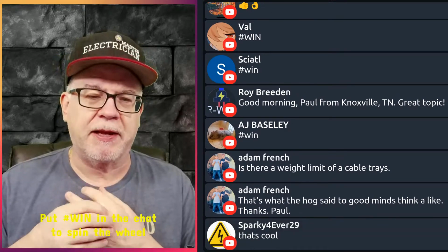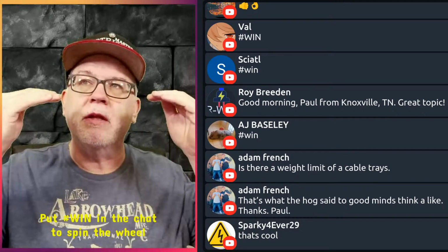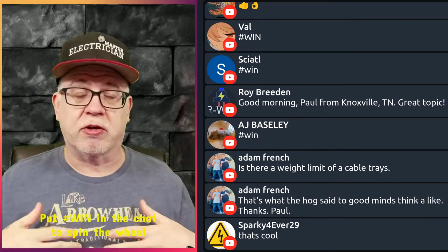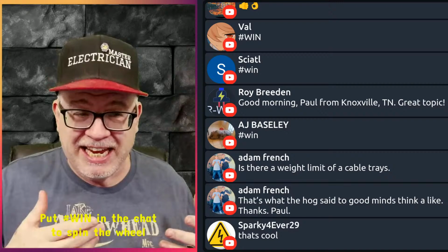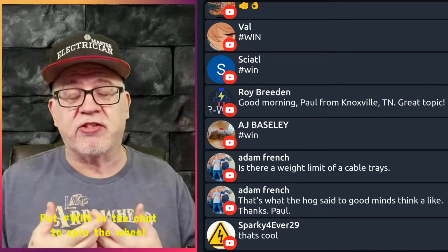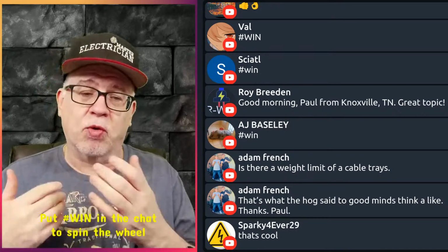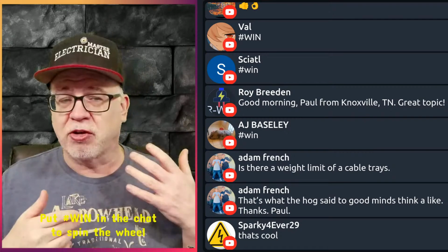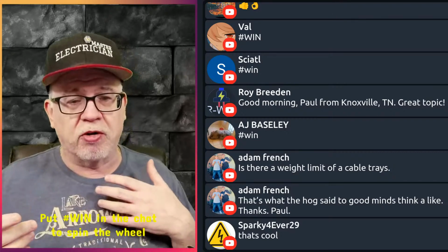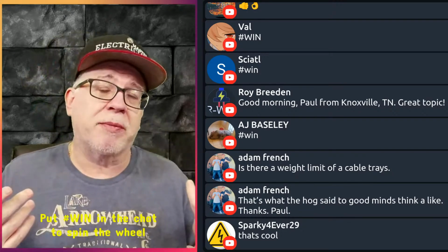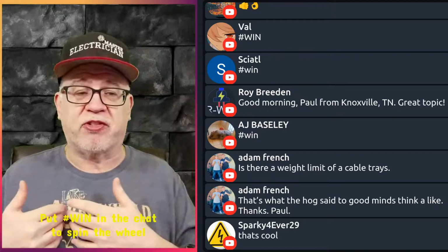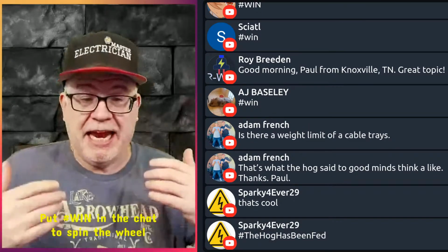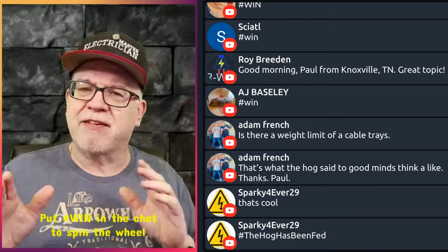So remember what I talked about yesterday? I said that cable trays are designed for cables. So we showed you the example of when you could put single conductor cables or single insulated conductors in a cable tray. That was in an industrial establishment. You and your AHJ have to work that out. If you manufacture a product, it's not just like a Walmart or a retail store or a mall, then it's probably not going to be an industrial establishment. And then you're not going to be able to put single insulated conductors or single conductor cables inside of the cable tray. Now, can you? I mean, you can, but will it pass inspection?